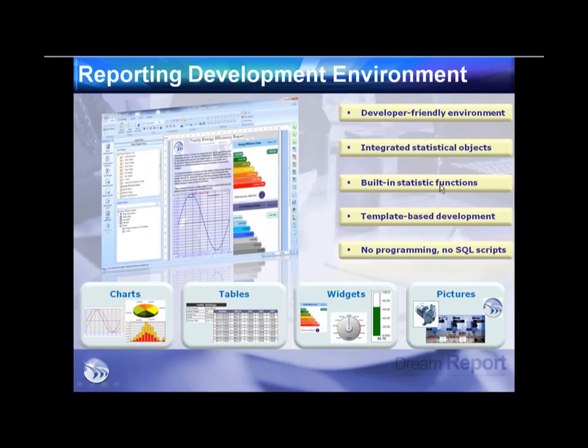All calculations are built-in statistical functions. For example, 15-minute averages are a checkbox — select average, set the step period to 15 minutes. Uptime, downtime, and percentage availability for a piece of equipment are likewise checkboxes. No programming, no SQL scripts required. If you do need a SQL command or stored procedure, there is a SQL object available, but most reports will be completely SQL-free from the user's perspective.